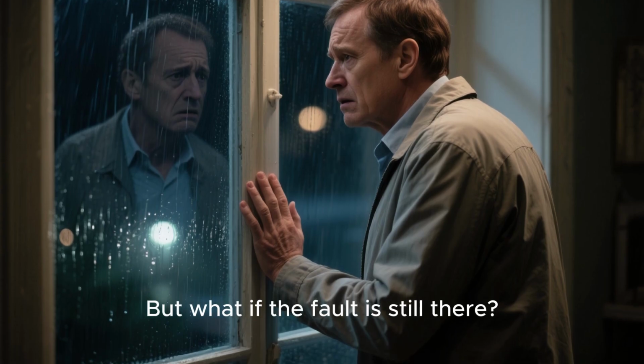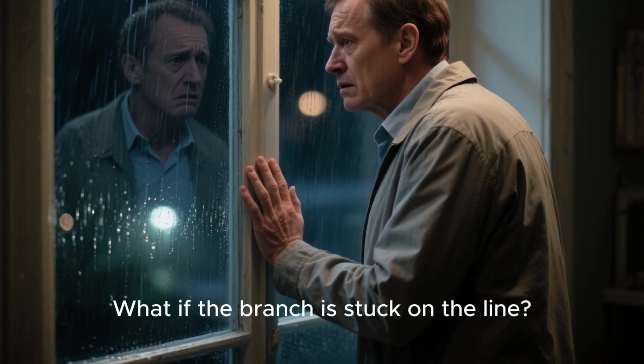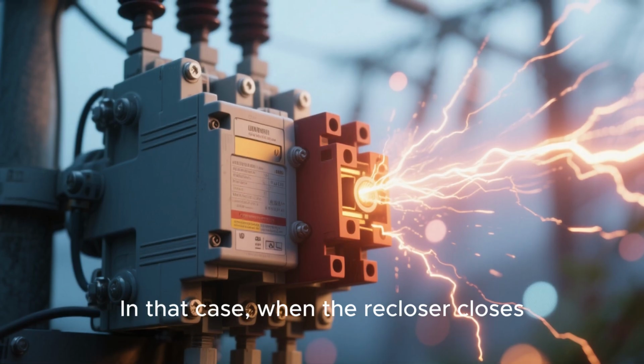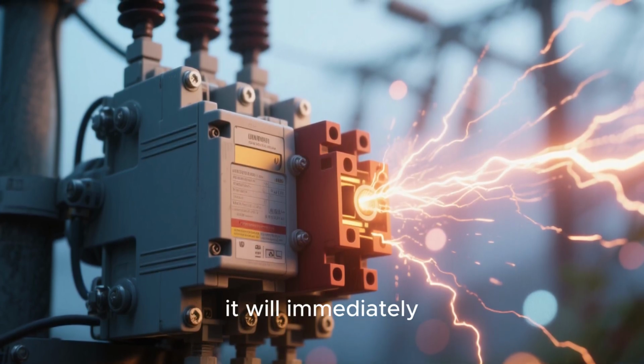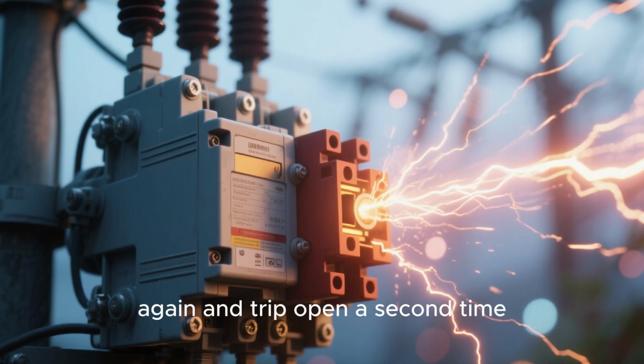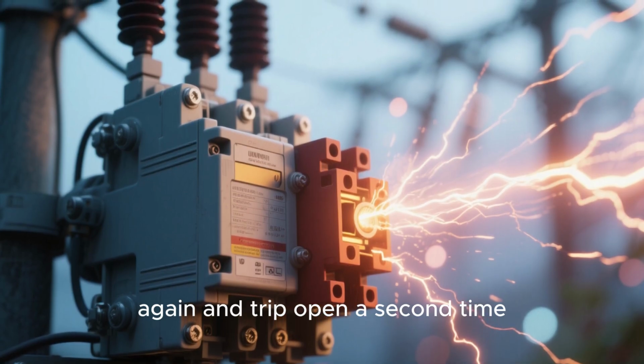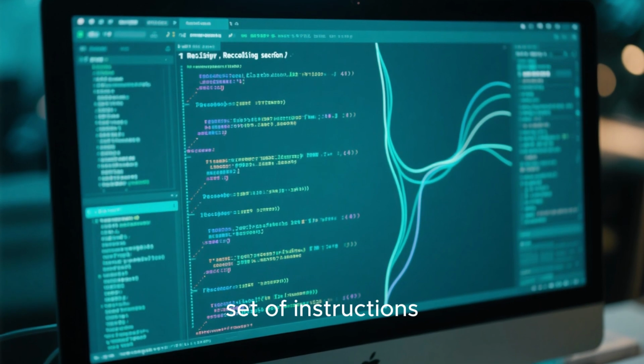But what if the fault is still there? What if the branch is stuck on the line? In that case, when the recloser closes, it will immediately detect the overcurrent again and trip open a second time. This is where the reclosing sequence comes in. This is a pre-programmed set of instructions that tells the recloser how to behave.